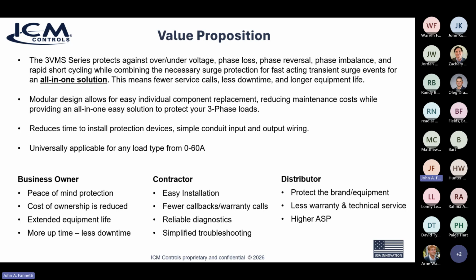So the value proposition: the 3VMS series protects you against over and under voltage, phase loss, phase reversal, phase imbalance, rapid short cycling, while also protecting you against those fast-acting transient surges that can really take out electronics very fast. So you want to protect the compressor and electronics not only from voltage issues, but also from surge-related issues. Each one has its own importance, as we talked about.